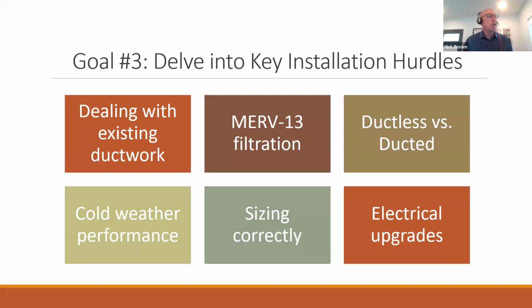All right, so these are the installation hurdles we wanted to focus on today that we hear all the time. Dealing with existing ductwork, what MERV 13 filtration means and its implications for overall system sizing, ductless versus ducted choices. You saw in the video there's a bunch of different configurations. We want to make sure you know what's out there, because it isn't just the high wall unit or some central ducted heat pump. There are a lot more choices than that. We'll talk about cold weather performance, best practices for sizing, and what to do when electrical upgrades seem to be needed to fit the heat pump on your panel.